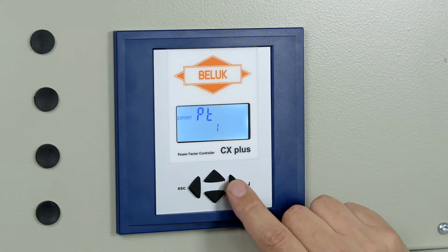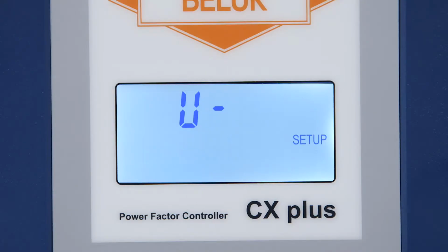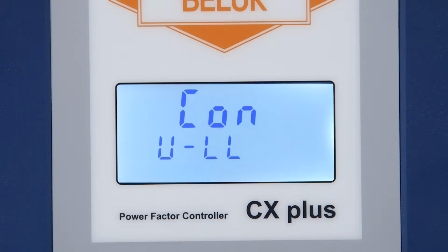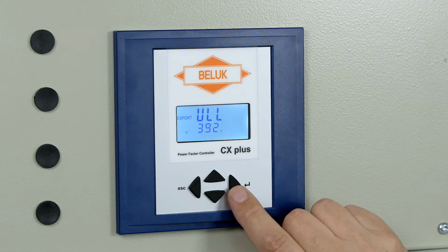Once the parameters UN and PT have been entered, the CXplus recognizes and indicates the type of connection of the voltage measurement. The user confirms this setting or corrects it. The measured ULL value is now displayed for 3 seconds. This serves as a check of the correctness of the previous entries.